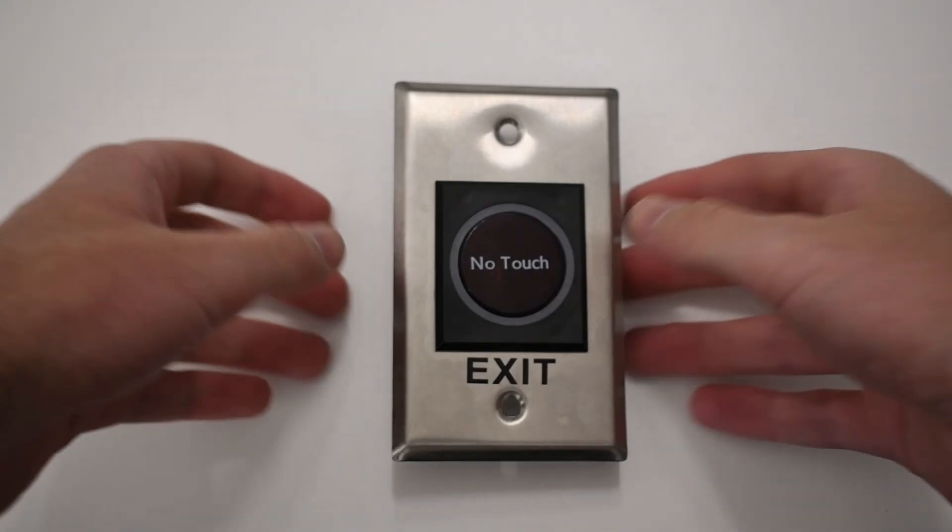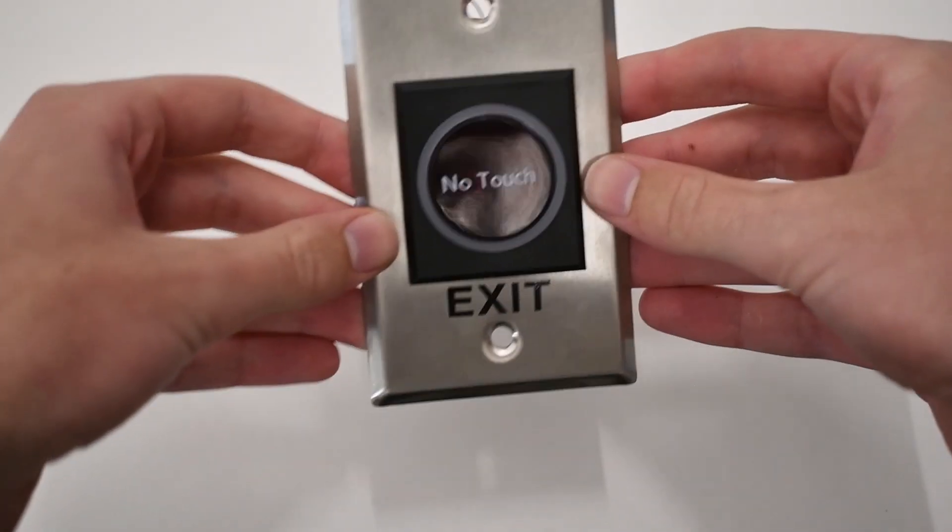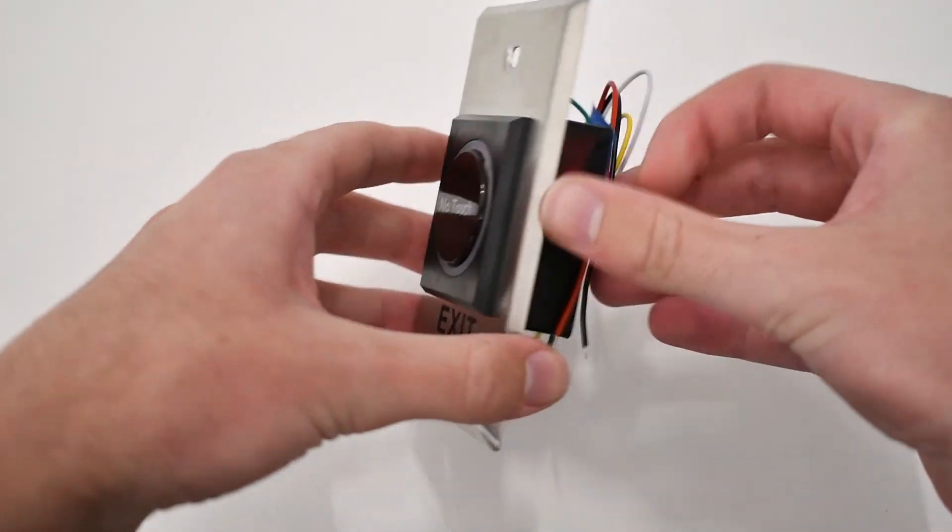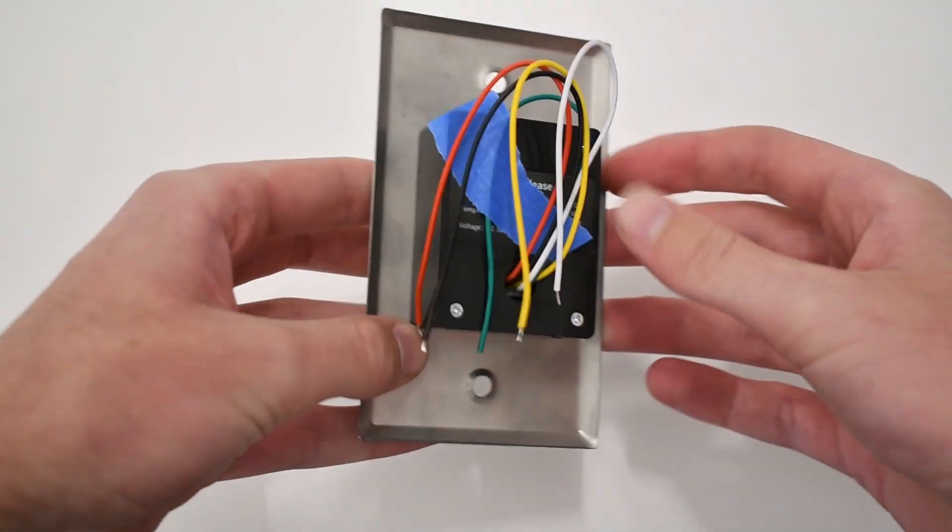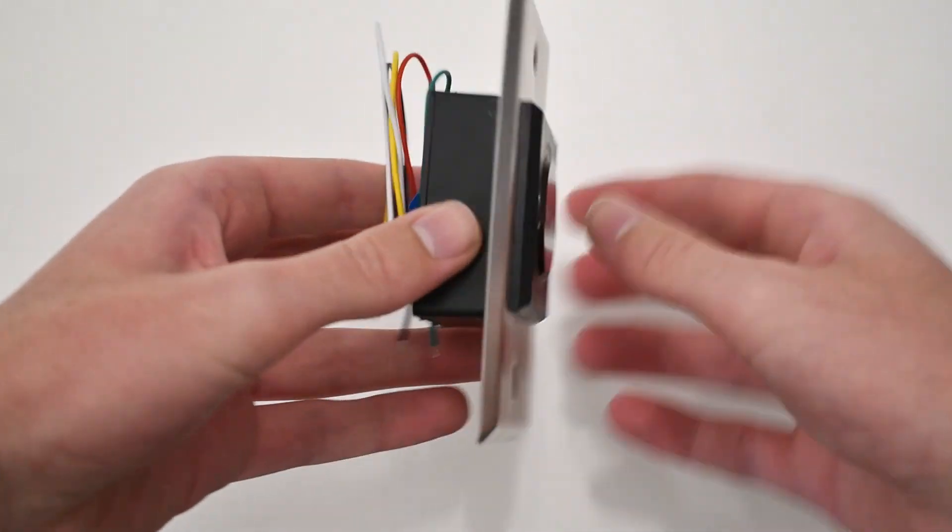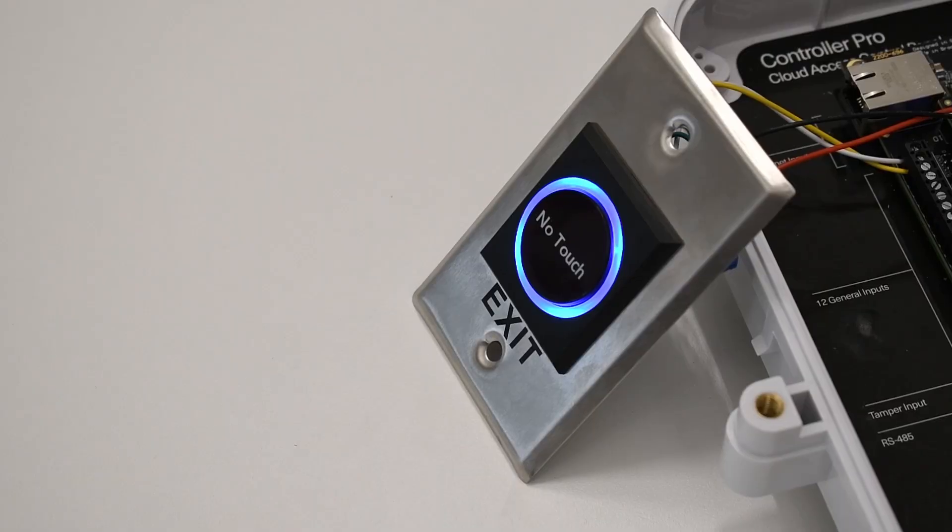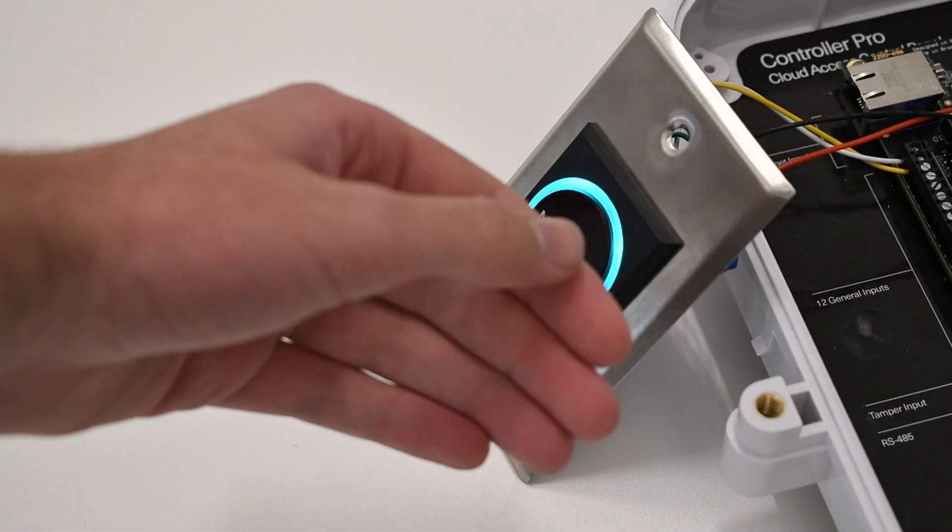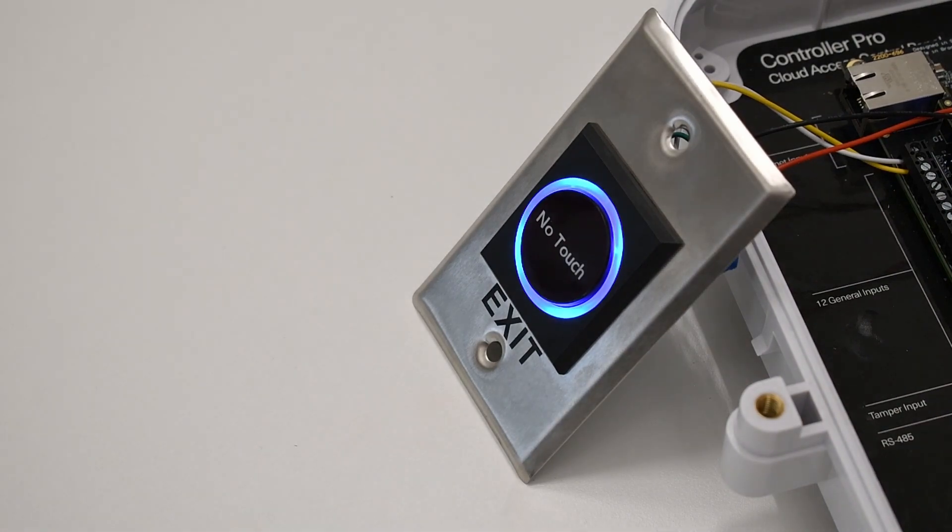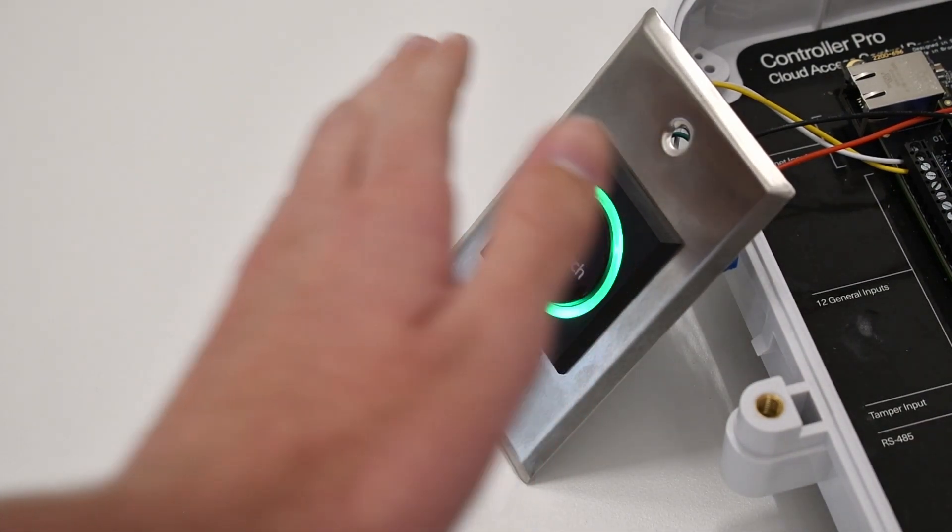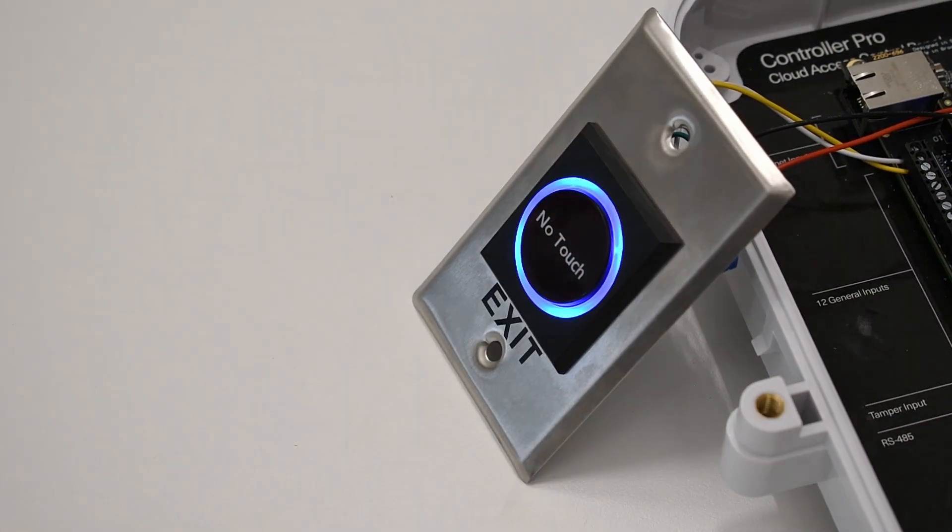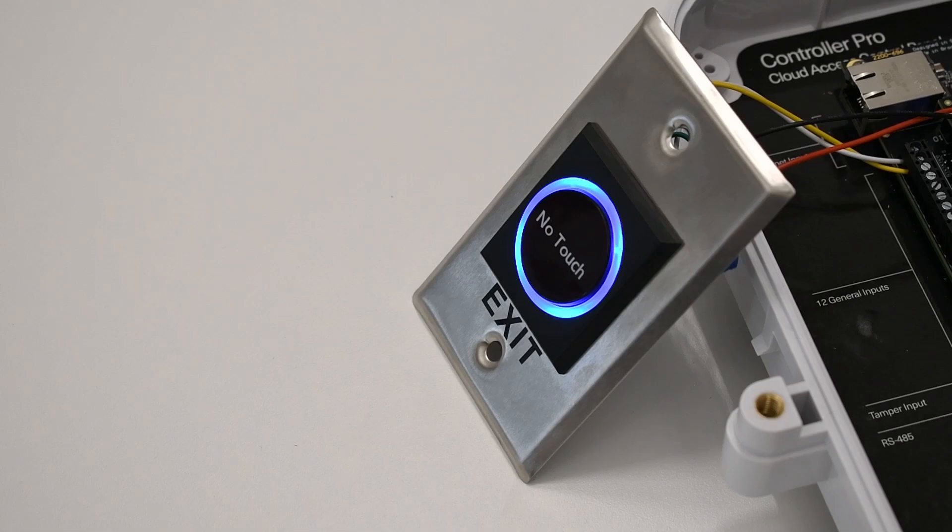A request-to-exit device like a no-touch exit allows you to open a locked door to exit without needing credentials. A no-touch exit device will sense if someone's hand is within 6 inches or 15 centimeters and automatically unlock the door so that they can exit. Push-to-exit buttons and motion sensors are some other common request-to-exit devices.